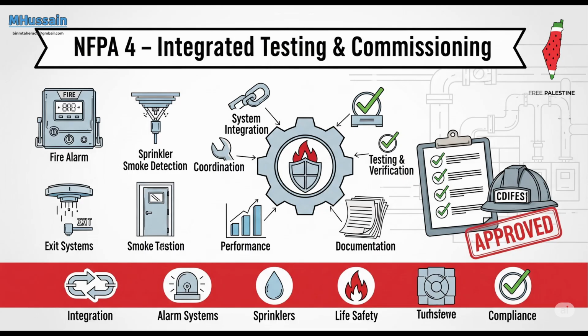What's that exactly? Think of it like the detailed script. It shows all the possible system inputs, like a smoke detector activating, and then lists all the associated output functions that should happen because of that input. So like input smoke detector floor 5, output alarm sounds floor 5, elevators are called to lobby, smoke dampers close floor 5. That level of detail. Precisely that level. It's the exact choreography of the emergency response.